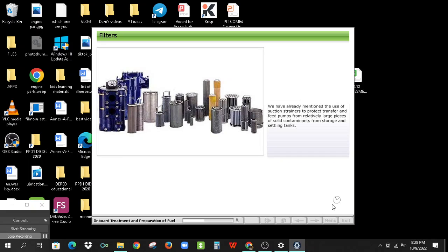We have already mentioned the use of suction strainers to protect transfer and feed pumps from relatively large pieces of solid contaminants from storage and settling tanks. We also need other strainers, often referred to as filters, in different parts of the fuel system to ensure the fuel is clean enough to use and to prevent components from being damaged. The majority of filters used in the fuel system will be some form of metal mesh basket or candle type if they are reusable, and paper or felt types if disposable. Click on the buttons to find out more about the different types of filters and the reason for having them.